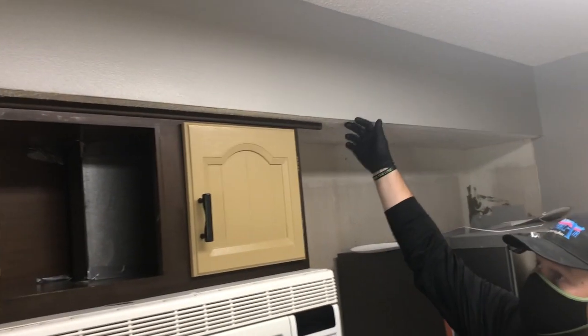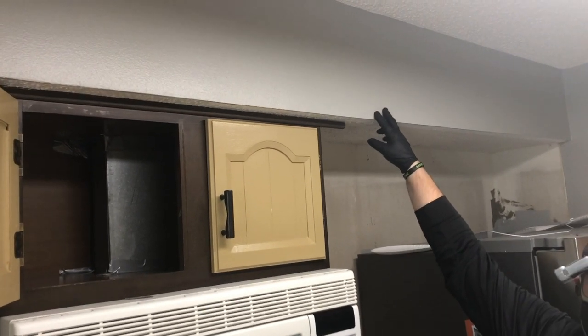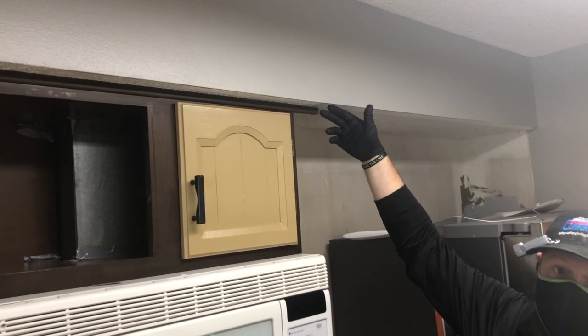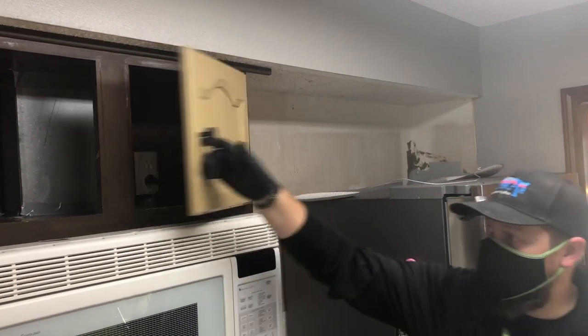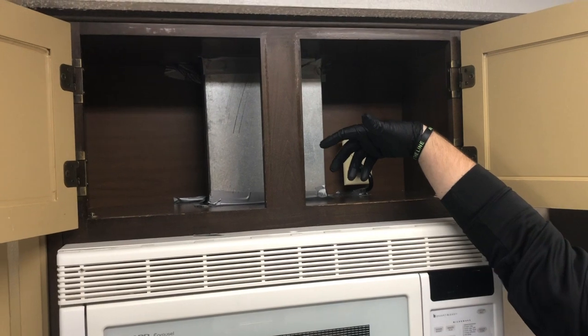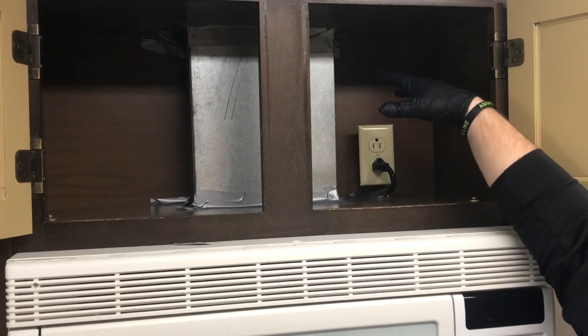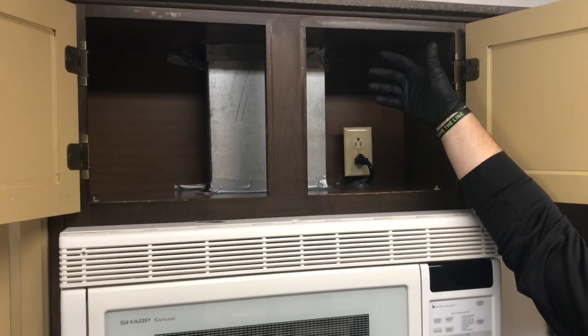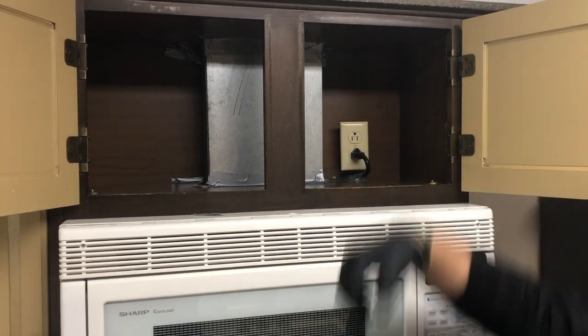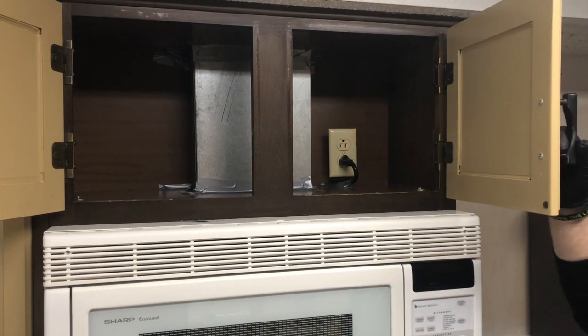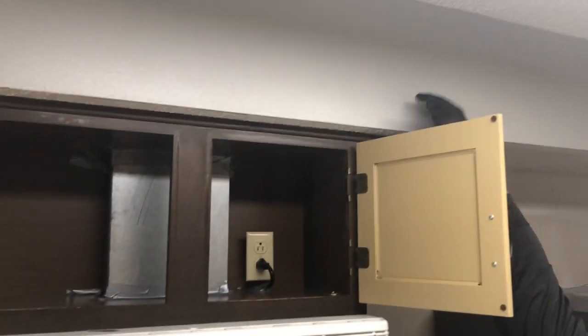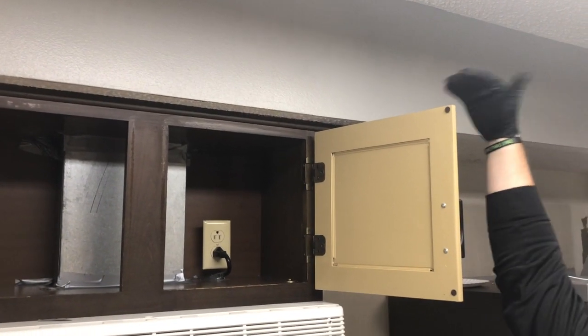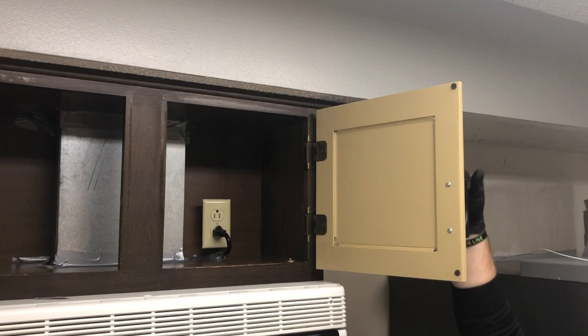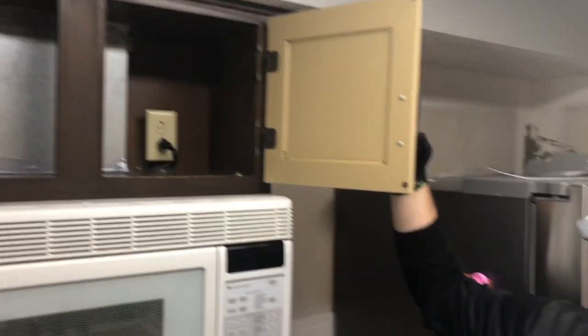Yep. One major concern we had was with these drop downs, these fur downs, these bulkheads that we see in many, many homes, is they never get sealed. So they're actually open to your attic. What was happening here before is we were getting a lot of infiltration and exfiltration from the home that was moving the hot, humid, or cold air from the attic to the living space. What we actually did was we sealed the very, very top. We made this actually part of the house now, and we did a 2-part closed cell spray foam to seal up the space.